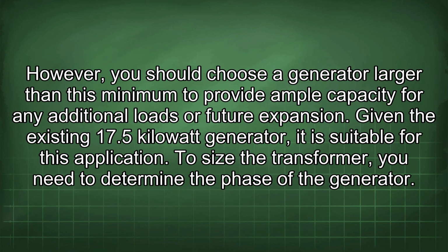However, you should choose a generator larger than this minimum to provide ample capacity for any additional loads or future expansion. Given the existing 17.5 kilowatt generator, it is suitable for this application.